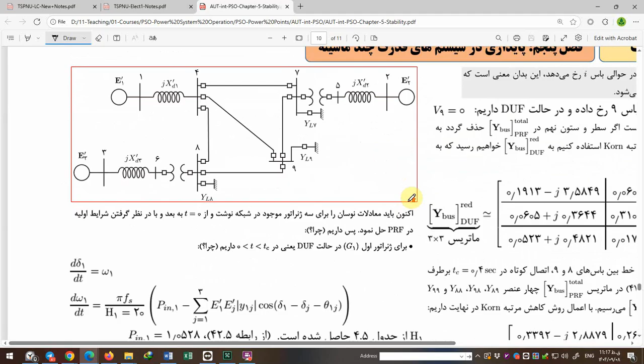Okay, so we can find out the synchronism between two generators means delta I minus delta J. If delta I minus delta J is limited or oscillating within a limit band, this means that the synchronism of generators is established. But if delta I minus delta J is not limited or is gradually increasing, this means that these disturbances make the power system unstable.